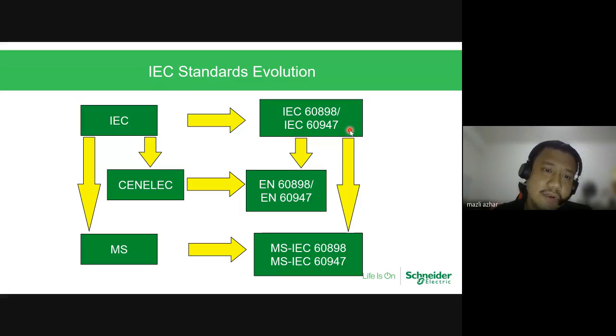Okay, standards evolution. Okay, just go a bit. You will have IEC, adopted by MS, becoming MS IEC. And one of the reasons why it is being adopted is that under Suruhanjaya Tenaga, or the Energy Commission, it is being regulated. This kind of breaker must have a serial label to ensure that it has been tested and is safe to be used by the end user.